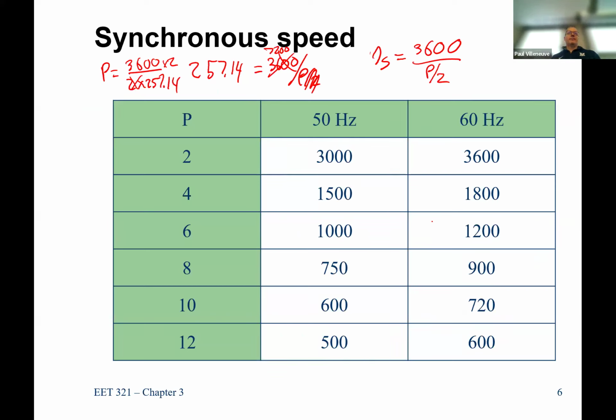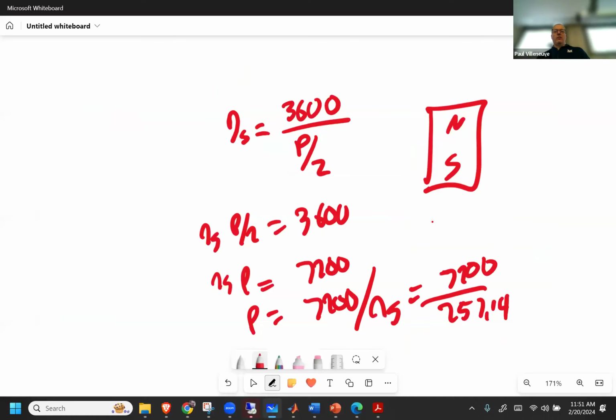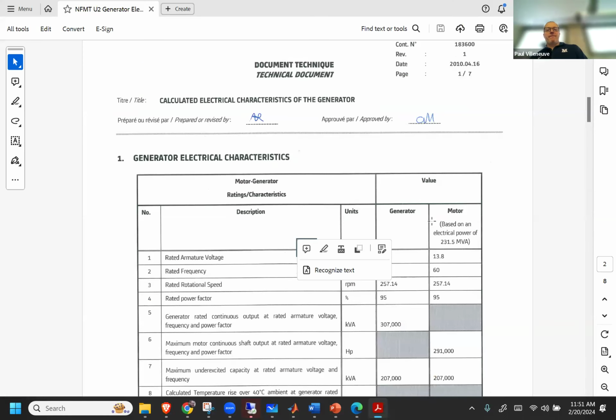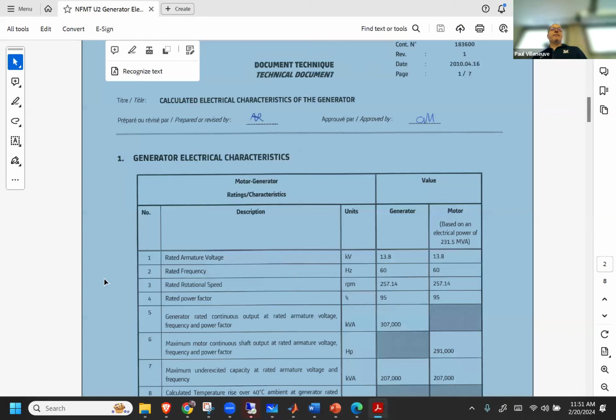So this is a 28 pole machine. Now you can calculate it. Hydroelectric facilities tend to have way more poles. Most reciprocating engines or gas turbines have 2 or 4 poles. A low speed diesel might run at 900 or 1200 RPM, but those are very expensive. If you go to Milton Cat or Caterpillar and want a 2 megawatt generator, it'll most likely be 1800 RPM. You can check if you want, and if we have time after class, we'll do that.